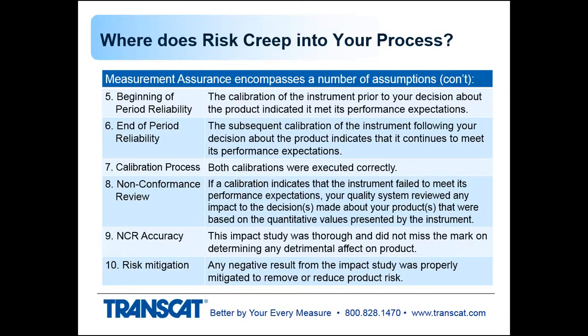Number 8 is nonconformance reviews. This has to do with remedial actions if the calibrated instrument fails to meet the performance expectations. Then you've got to be able to execute in a timely manner a nonconformance review of those out-of-tolerance conditions to determine if there is any impact on the product that gives it a negative impact for the decisions made about the product. So that leads to number 9, which is the accuracy of those nonconformance reviews.